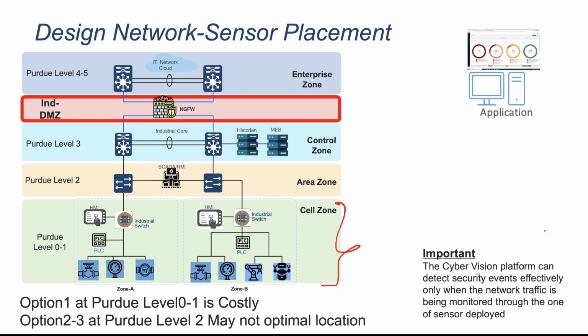If we collect from the Purdue aggregation layer, then it will only give the north-south traffic, that is, traffic going out of the network. It won't capture the traffic between the PLCs and various devices. Instead of creating an OOB network, we can also try to use RSPAN in the network, but normally RSPAN is to be avoided, as it creates jitter.